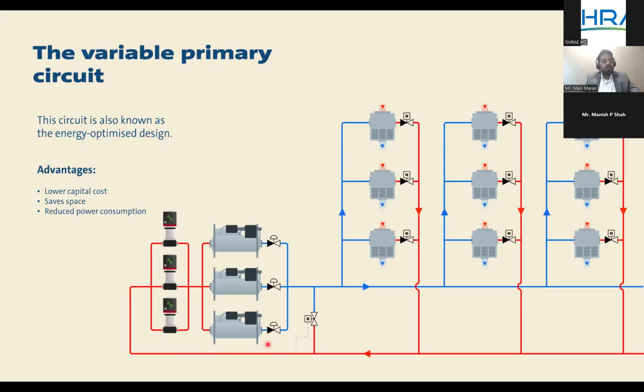So let's see the variable primary design first, before moving to distributed pumping with variable primary as a concept. In variable primary, the pumps are designed for the capacity of the chiller. It can be one pump to one chiller, or a common headered system, and the flow is determined based on the tonnage of the chiller. The head of the pump is based on the friction from the pump through the entire load, maybe the critical load or furthest loop, back to the pump. That's how the head of the pump is calculated in a conventional design. Moving towards the secondary side, we have multiple individual units. It can be CDU, fan wall unit, or CRAH unit connected with a modulating valve and balancing valve. That's how the system on the secondary side is designed.